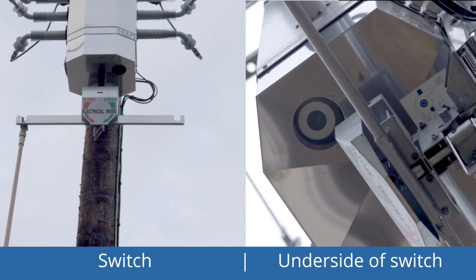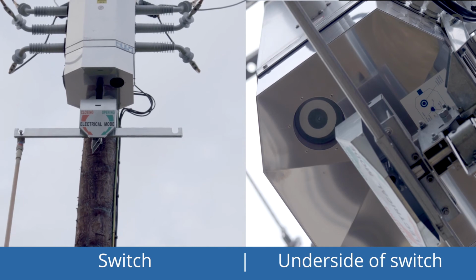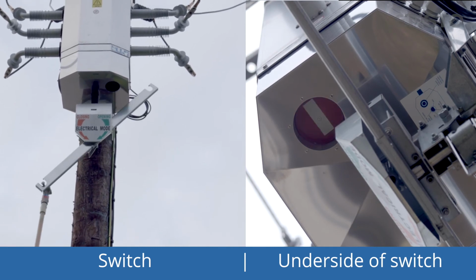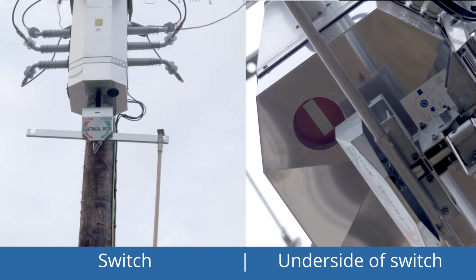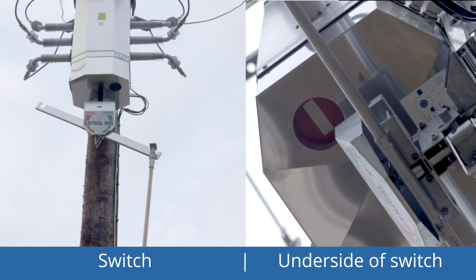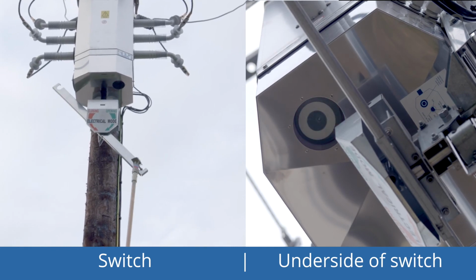Manual testing. The operating arm should be in the horizontal position. Using a set of insulated operating rods, pull down on the left to close, or pull down on the right to open. After each operation, observe on the underside that the mechanical indicator is in the correct position.